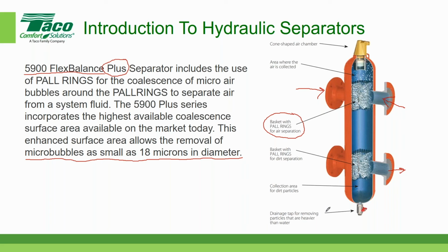And there is a drain valve at the bottom. In this case, it's actually a drain tap that you can add a valve. And that's so you can blow out the dirt that's collected by the separator, and then there is an air vent at the top. This uses a float device. You can see the float right in there. So as air collects at the top, the float will drop down, opening the valve, the air escapes, and as the water comes up, it pushes the float up, closing the valve, keeping the water from escaping. So it's a very efficient device.